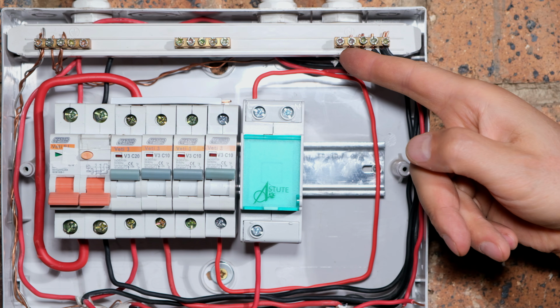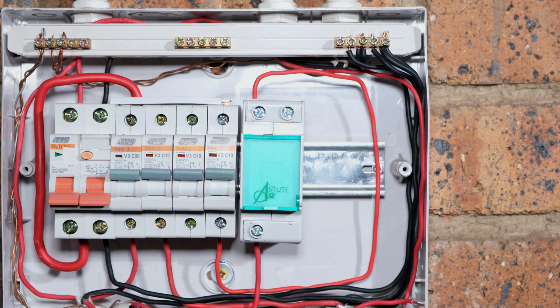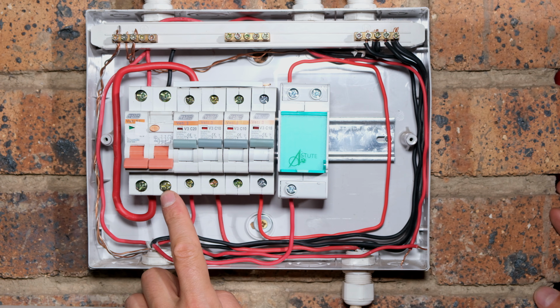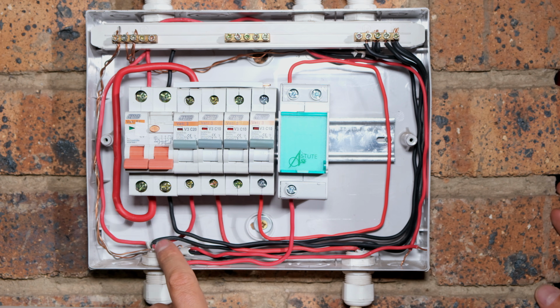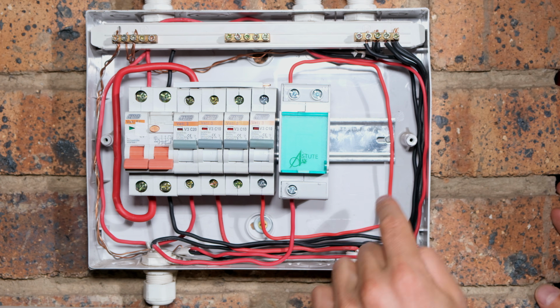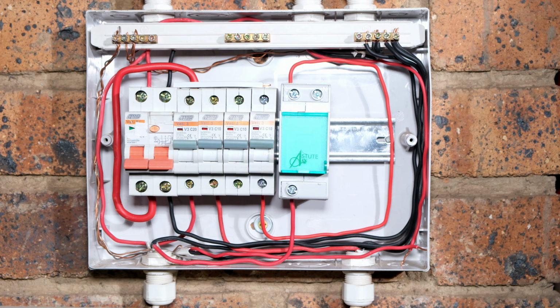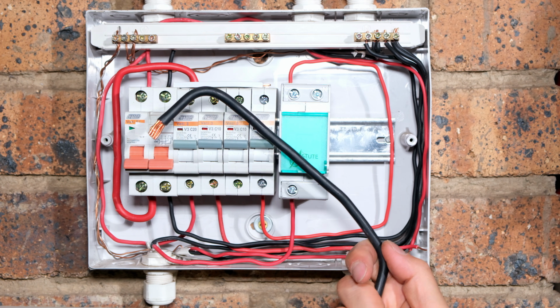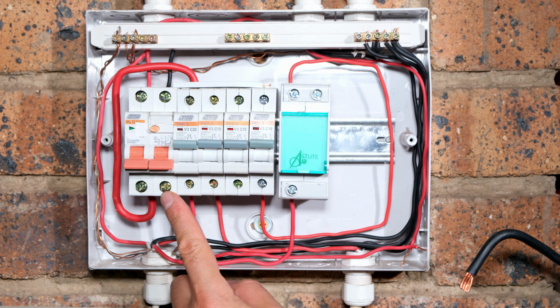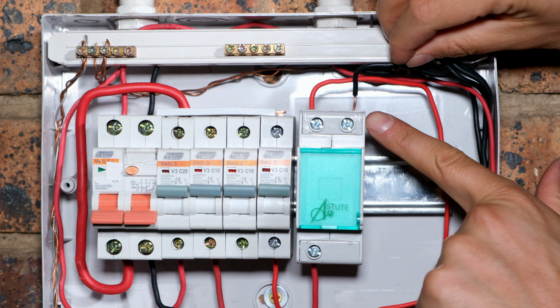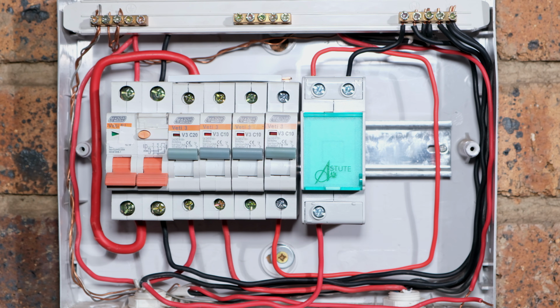In this case, all the neutral wires are sitting here. If you're not sure which is the neutral, you can always look at the output of your main breaker, and there is the black wire, and it is going all the way to the top here. In a bigger distribution board, you'll find your neutral wire looks like this. That's coming from the main breaker. So I just need to go from there to there. Right, so the timer has actually been wired now. So if I lift this up, the timer should go on.